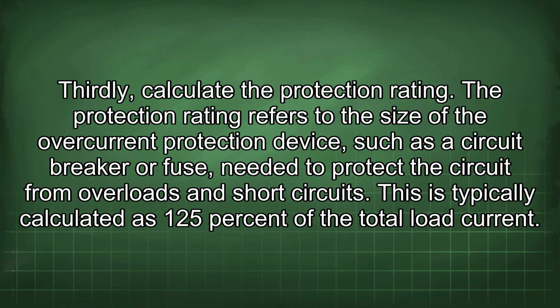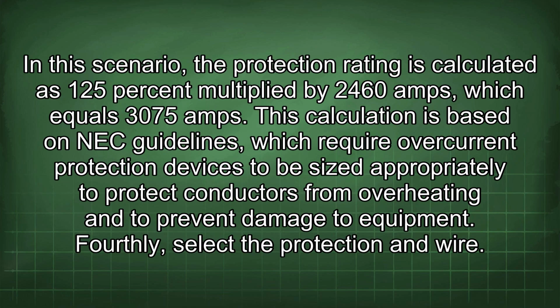Thirdly, calculate the protection rating. The protection rating refers to the size of the overcurrent protection device, such as a circuit breaker or fuse, needed to protect the circuit from overloads and short circuits. This is typically calculated as 125% of the total load current. In this scenario, the protection rating is calculated as 125% multiplied by 2460 amps, which equals 3075 amps.